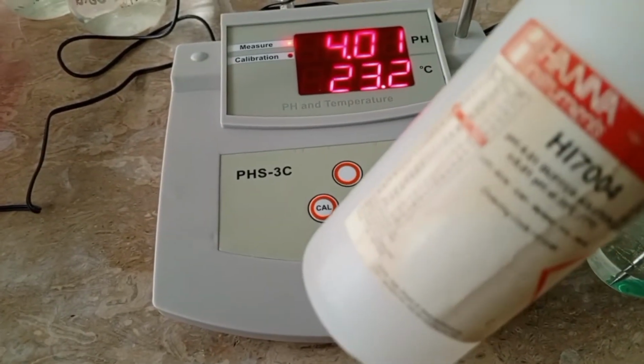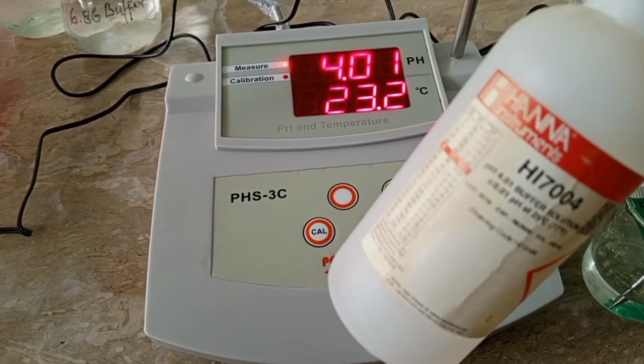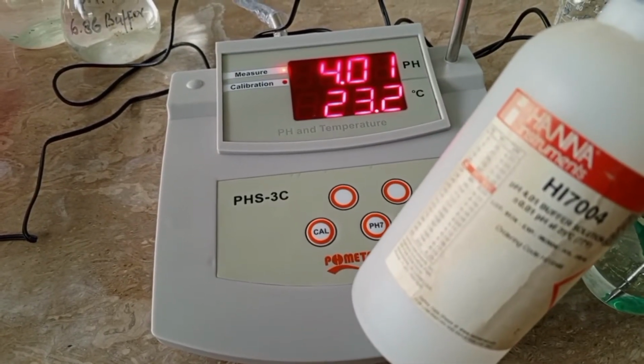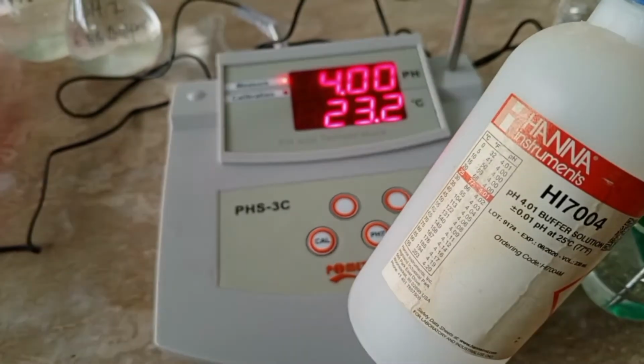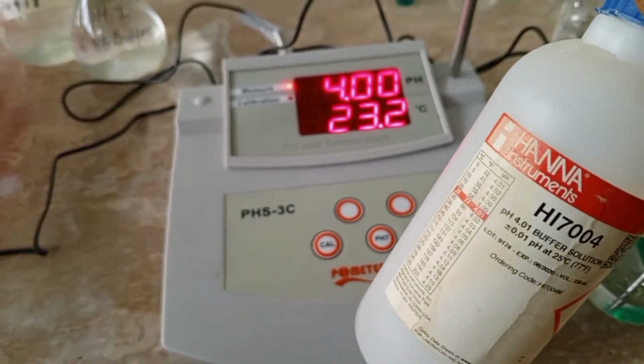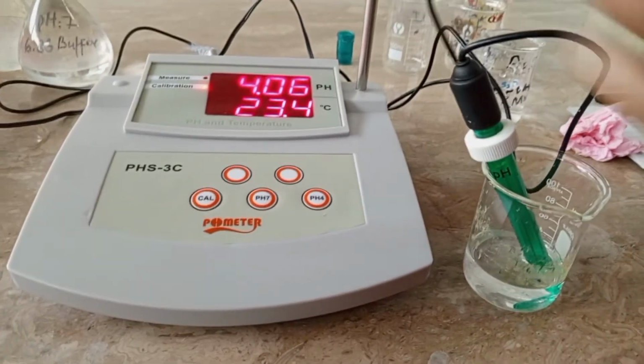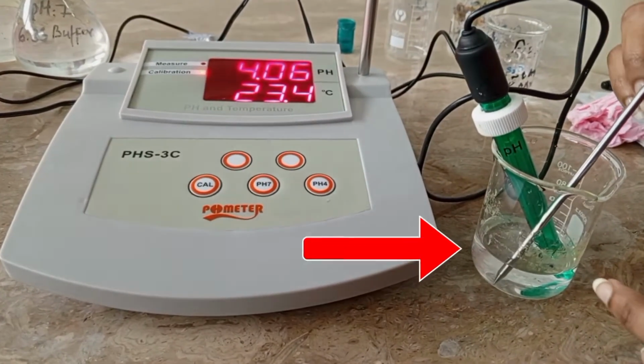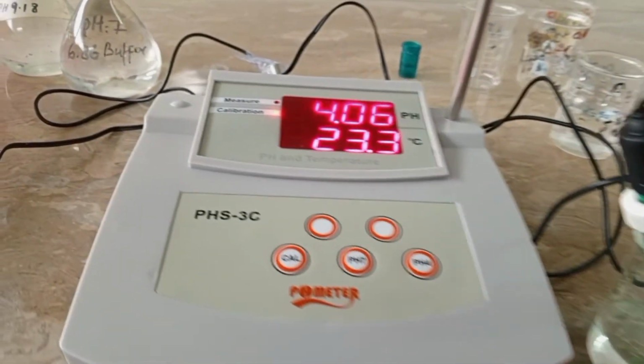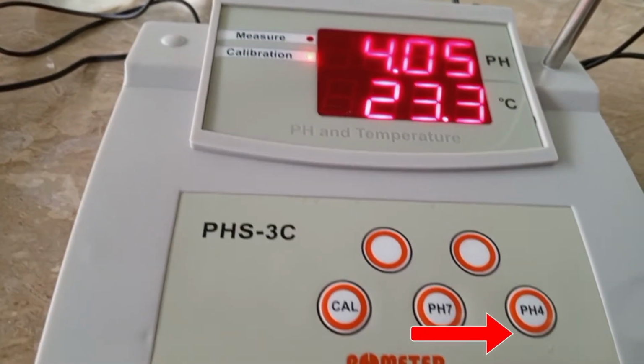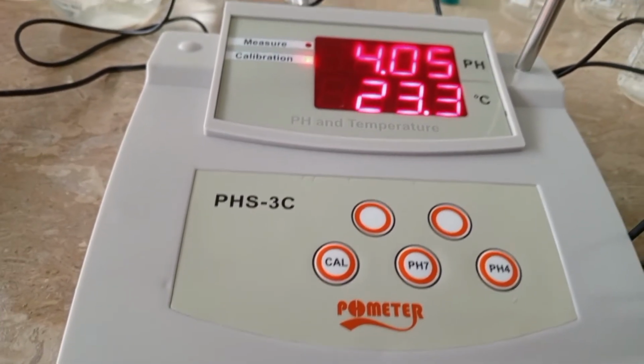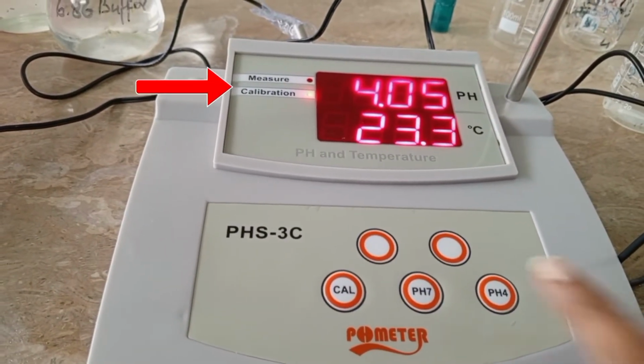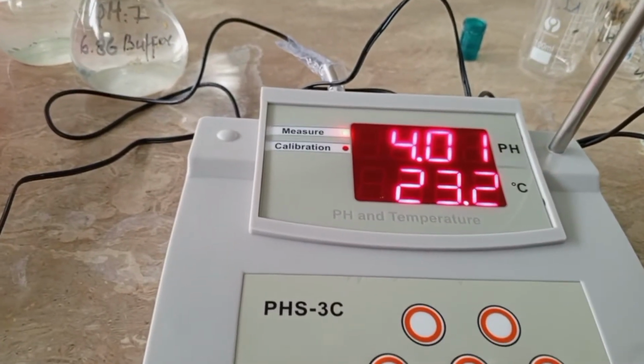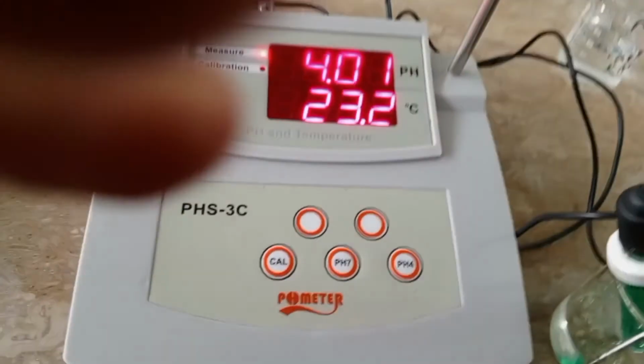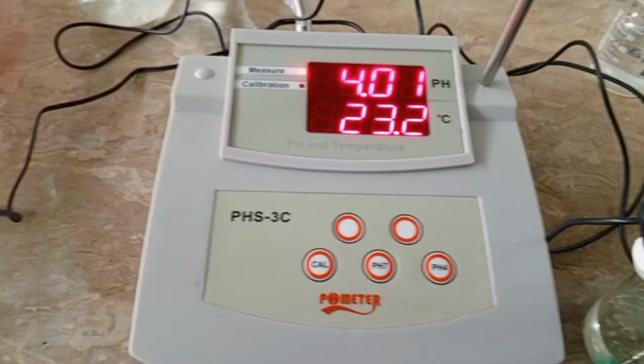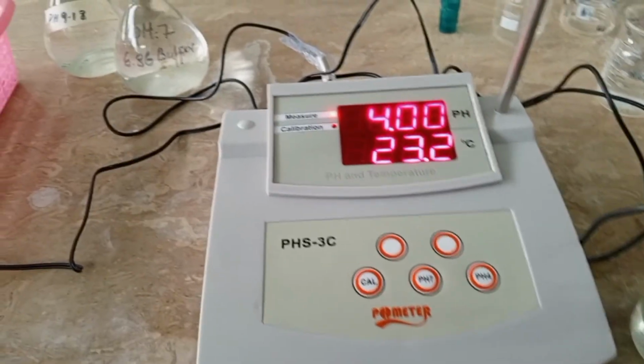Take a calibrating solution of pH 4.01 buffer. On its bottle, pH values with respect to temperature are also written, so you can compare the value of pH with respect to a particular temperature. Now dip the electrode and temperature probe in the calibrating solution and press the pH 4 button. The red light again returns to its initial state of measure, and the instrument will show you the calibrated solution of 4.01, or about 4 pH.